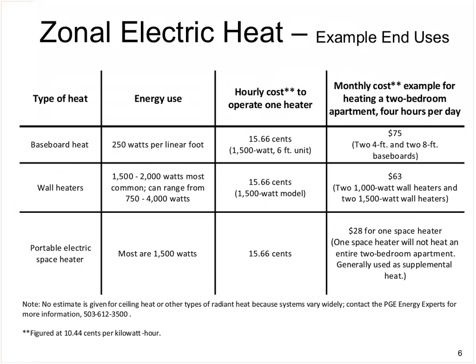Wall heaters are another common heat source. Often you'll see them with a blower motor or a fan. Wall units generally range between 1,500 and 2,000 watts. The range can be 750 to 4,000, though. So the hourly cost to operate a 1,500-watt model would be the same as the baseboard, 15.66 cents.